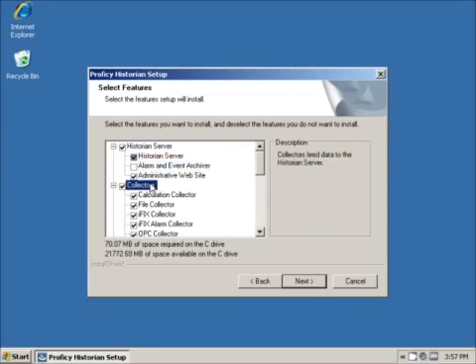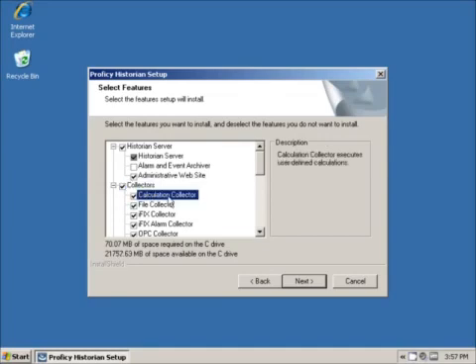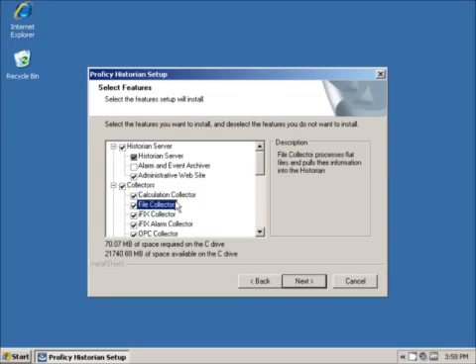The collectors are used to retrieve data from specific sources and send it back to the Historian. The Simplicity collector is installed with and enabled from Simplicity itself. The Calculation collector is a transformation collector. It is designed to retrieve data from the Historian and calculate a new value which it stores in another tag. This is a licensed option included in the Enterprise version. The file collector is designed to import data into the Historian from properly formatted CSV or XML files, allowing lab and other data to be included in the Historian, as well as for importing from other sources.